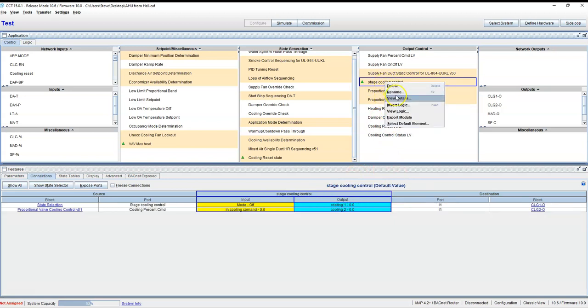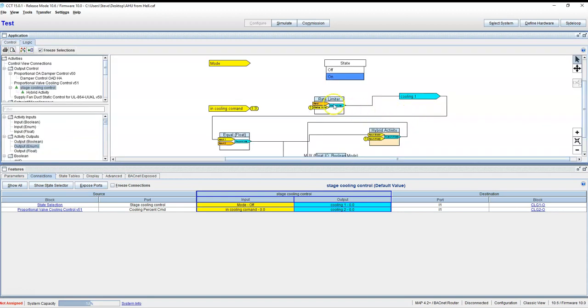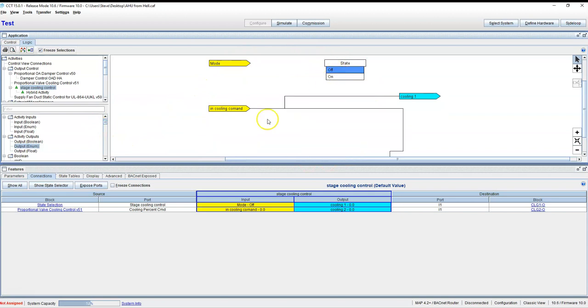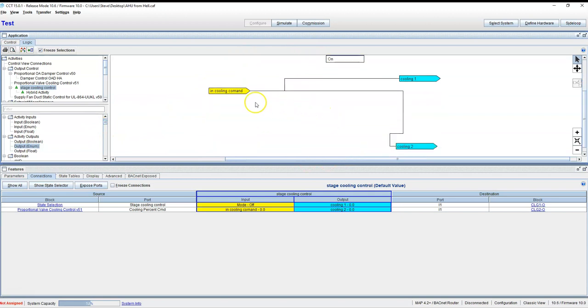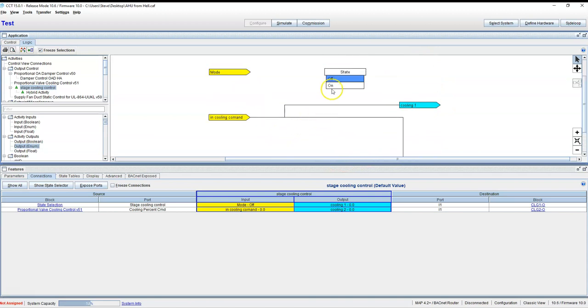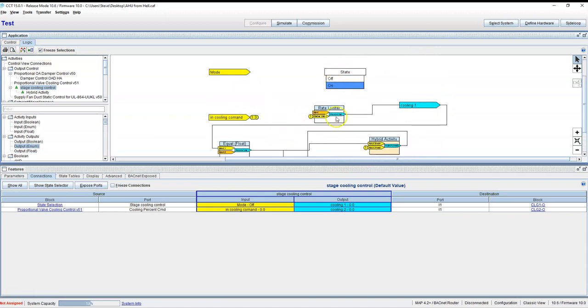So we went with a hybrid activity block. In off mode, our proportional valve cooling control is just going out to our cooling valves to maintain discharge air temp. But whenever we go into optimization mode, we got a rate limiter here.